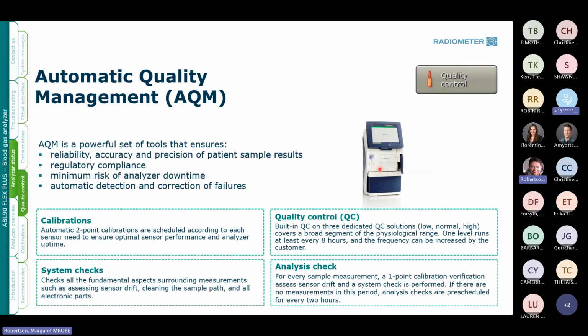So the next part of it is the ABL is managed by an automatic quality management system. And what comprises that automatic management system for the analyzer is calibrations, system checks, quality control, and analysis check. So the calibrations, an automatic 2-point calibration, are scheduled according to each sensor's need to ensure optimal sensor performance on the analyzer for uptime. System checks are performed once a day, so every 24 hours this one gets done. We usually set that up so it happens in the middle of the night so that it doesn't fall into a point in time that's going to cause problems in your workflow.